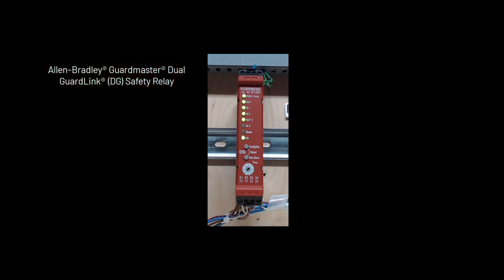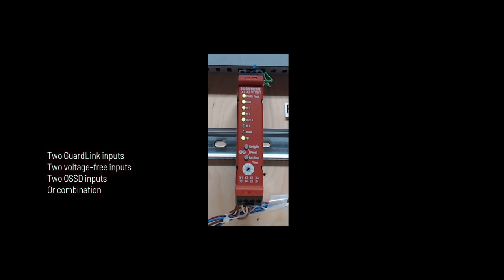This video will show how to configure the Allen-Bradley GuardMaster DG safety relay. The DG relay can accommodate one or two dual channel circuits. The inputs can be two GuardLink circuits, two channels with voltage-free contacts like e-stops, two channels with OSSD signals like sensor guard switches, or a combination of the types of inputs.